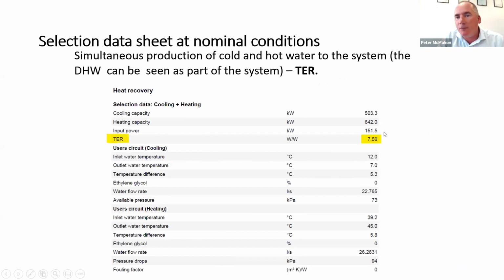The input power is 151. You now know these two combined divided by this gives your TER. This is a pretty much nominal condition. Supply 7, chilled water return 12, and supply heat, hot, warm water 45, back at 39. So pretty nominal conditions. Of course, if we change those conditions, it will increase or decrease the efficiency and the performance. Okay.